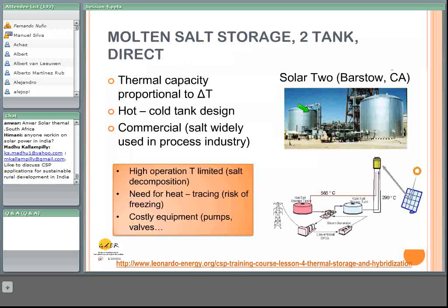And the limits for the operation are that the maximum temperature must be limited, because above these temperatures, this mixture may experience some decomposition. And of course, there's a need for heat tracing, because in case of a long period without solar radiation, there's a risk for the molten salts to freeze. That should be avoided, because it's very expensive to melt them again, very expensive in terms of energy and very costly also in terms of time and effort, and the equipment is rather expensive.